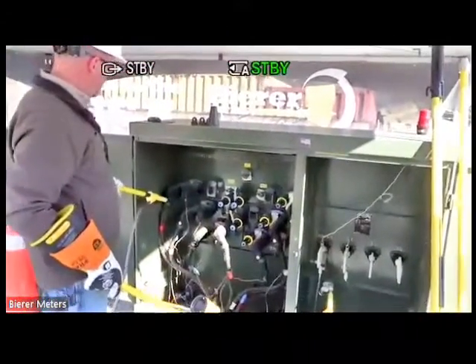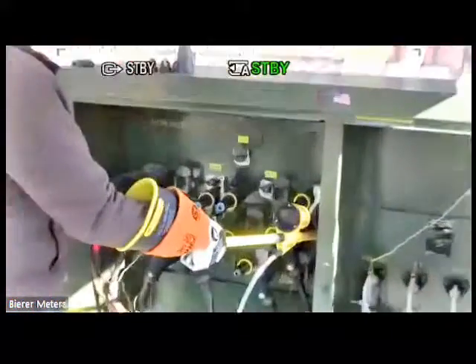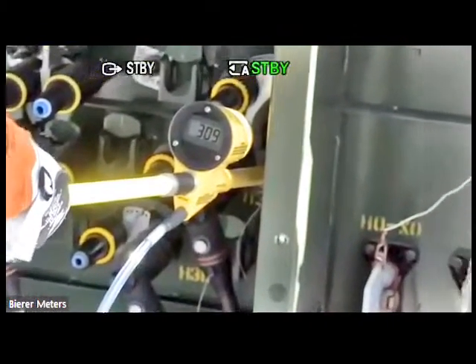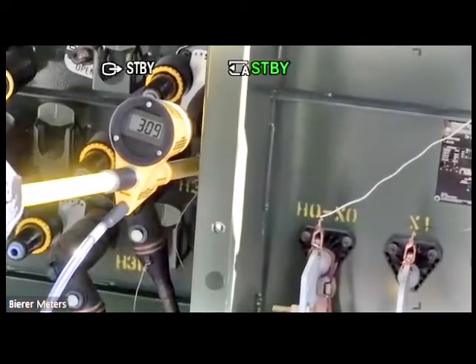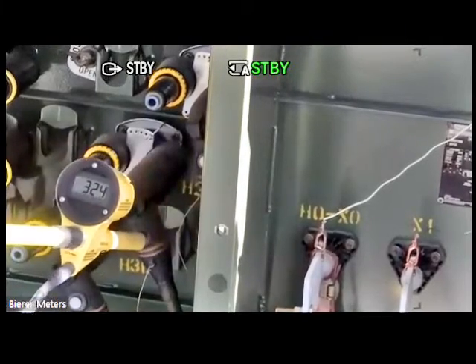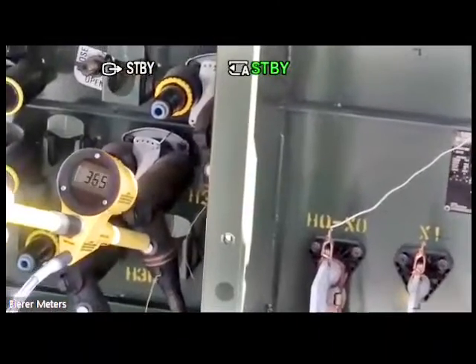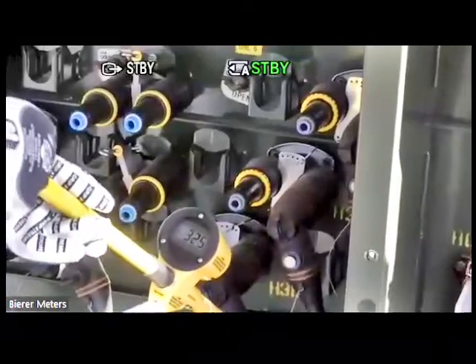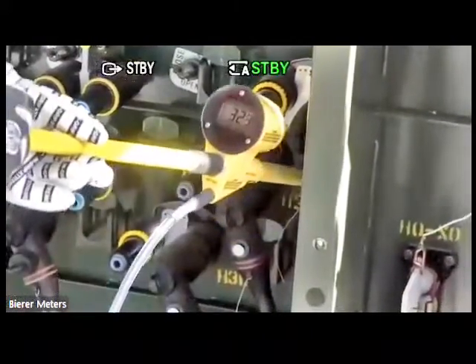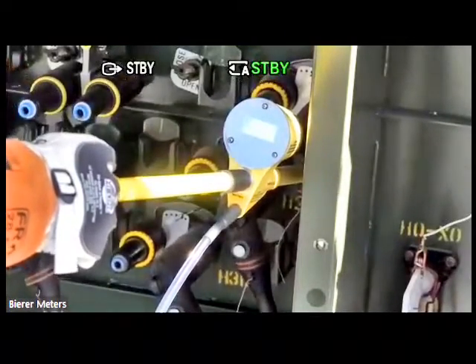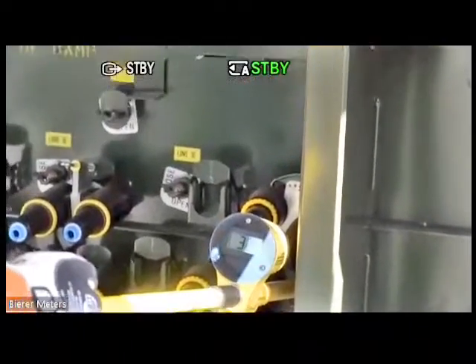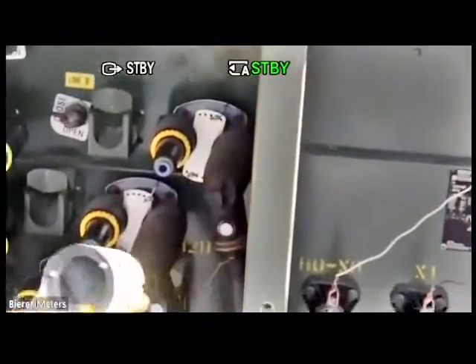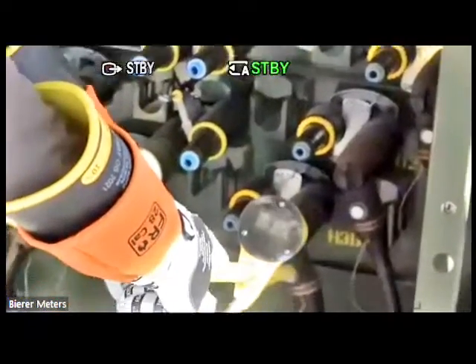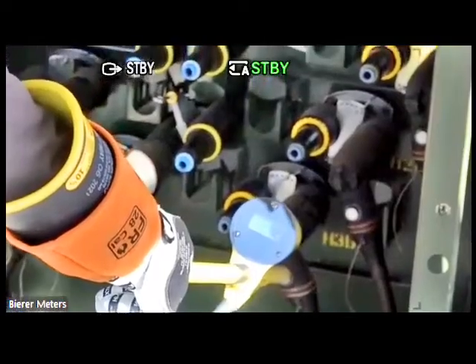All right. So if I go phase to phase, in phase, I should get some number less than that. And phase to phase, out of phase, I should get some number higher than that. So all those are roughly 340, 350, 360. There's phase to phase in phase and phase to phase out of phase. There's again my 366, 367, 370. But in phase, it's about 310. Okay, so that's your lower number. That's your in phase number. And if I move my second probe over here, you'll see that number go back up to your 360. If I find that blue phase over here, since this one was 360, it should be around 300, and there it is. That's my 312. So that's how you find your in phase number.